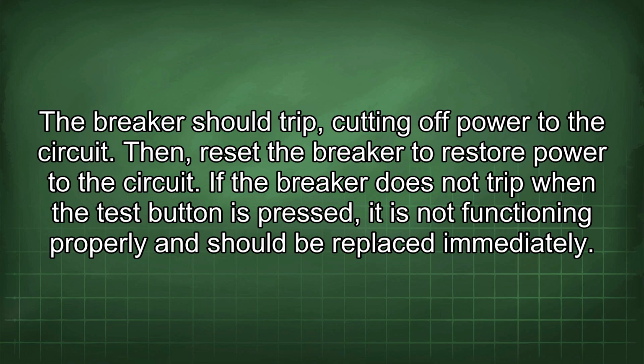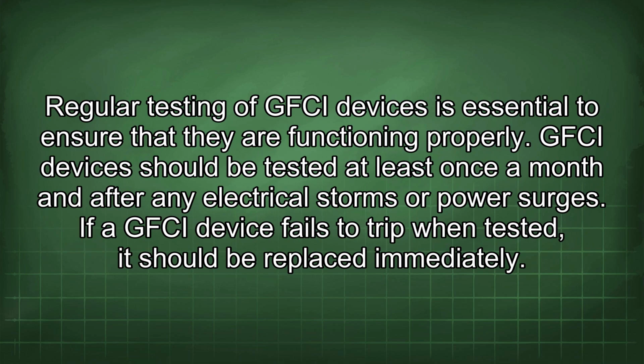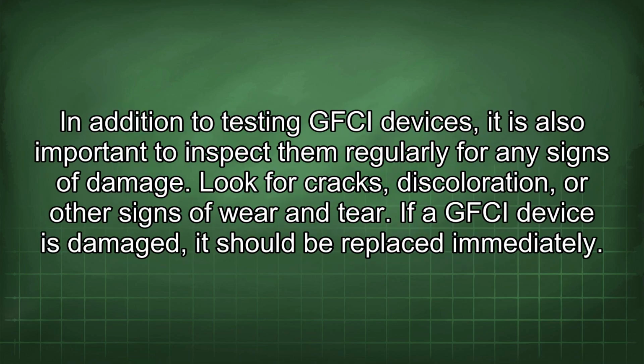replaced immediately. Regular testing of GFCI devices is essential to ensure that they are functioning properly. GFCI devices should be tested at least once a month and after any electrical storms or power surges. If a GFCI device fails to trip when tested, it should be replaced immediately. In addition to testing GFCI devices, it is also important to inspect them regularly for any signs of damage. Look for cracks, discoloration, or other signs of wear and tear. If a GFCI device is damaged, it should be replaced immediately.